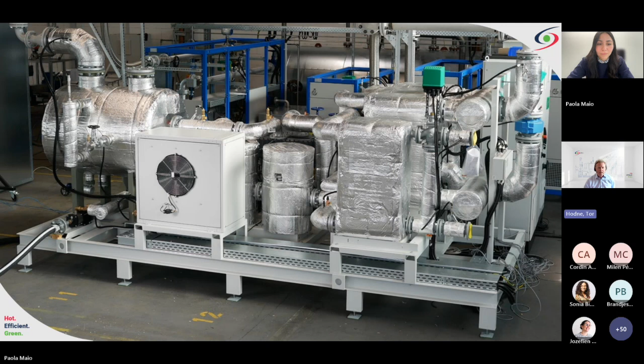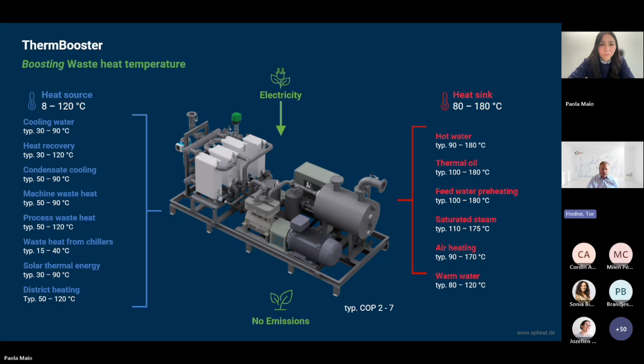As mentioned by Corden earlier, our ThermBooster heat pump is a very flexible technology which can run on a large variety of heat sources, anything from cooling water and process waste heat to solar and district heating. On the heat sink side, we can provide hot water, thermal oil, or saturated steam directly all the way up to 160, 170 degrees C.